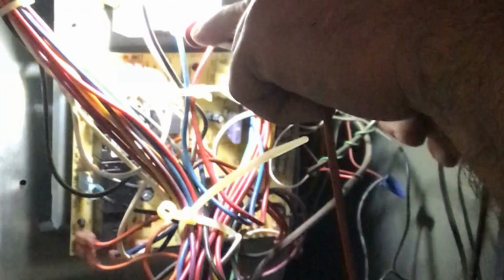So one of the easiest ways to check your transformer is set your meter to volts, and you want to test your output. Most transformers should be labeled which side is 24 and which side is 120 volts. If you do not have 24 volts coming out of your transformer, the next thing you need to check is to make sure it's being supplied from the circuit board. So your feed voltage for the furnace is going into the board first, and then it's coming out of a terminal typically labeled XFMR.